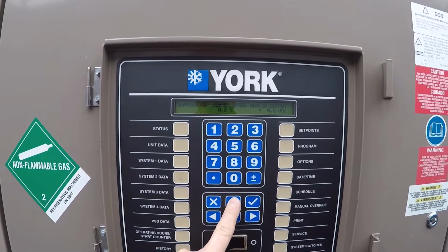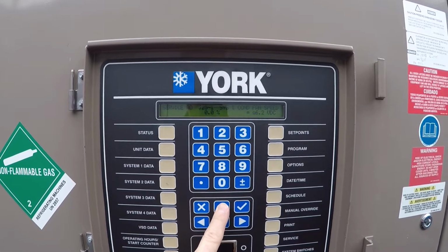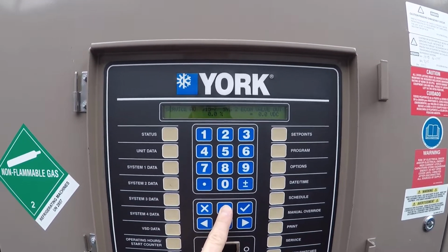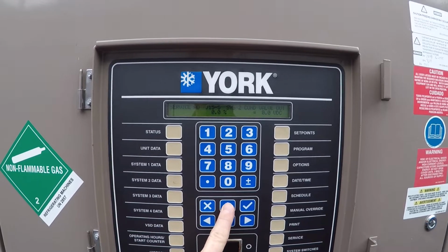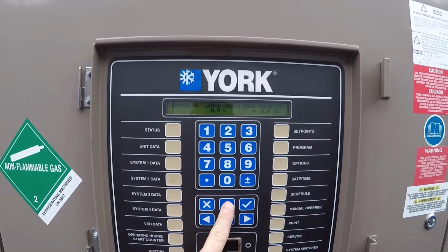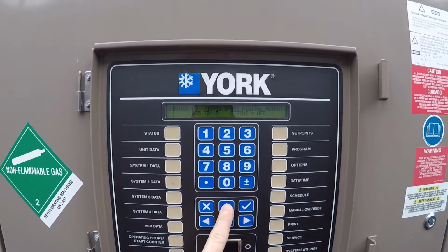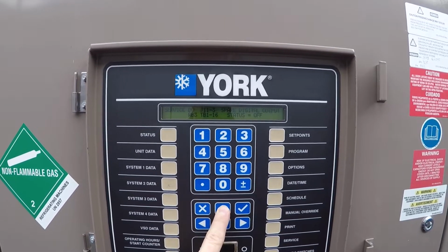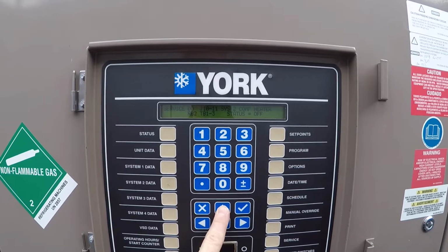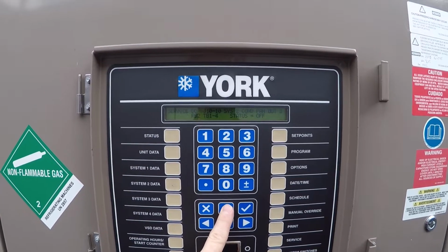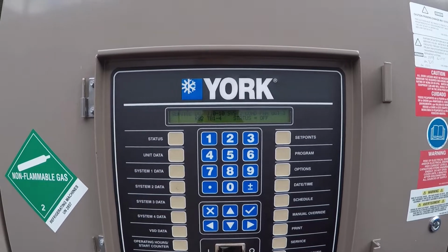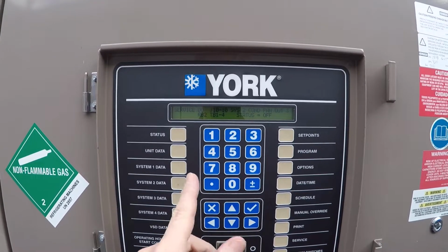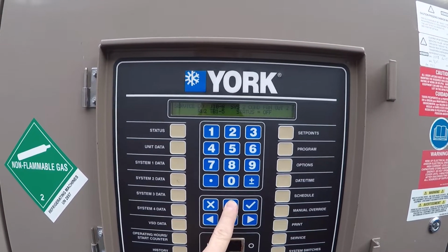As we work our way through all these inputs, we can make our way into the condenser fan section. There's a lot of inputs. So you can actually drive your economizer valves and your condensing valves. As you work your way, there's lots of stuff to go through, but your hand gets tired pushing the button so many times. But we will make it to the condenser fan section, and we can actually test the compressor heaters. We can make sure that they're working. Condenser fans, so system 2 and system 1, you'll be able to test all of them. So I push the button, the fan starts up, push the button, turns off, and I can go through and test all of them, and so on.